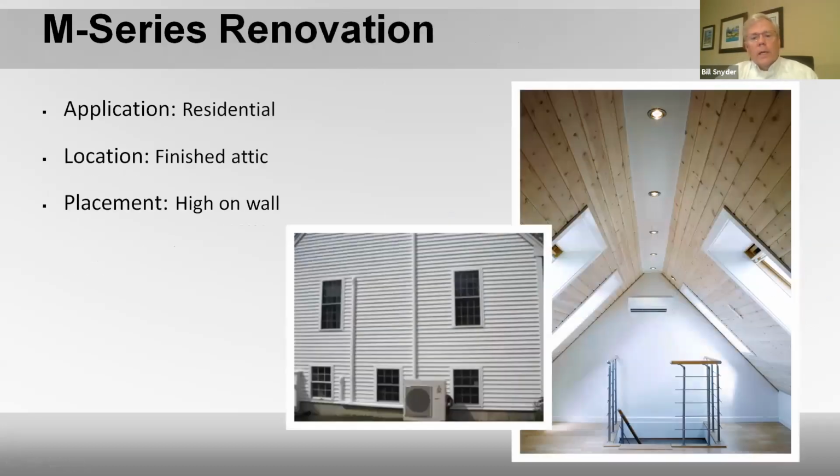And here's an example of an MXZ multi-zone unit. We know that because here's the outdoor unit, and here's line hide going up to this unit here on the 3rd floor. There's a unit on the second floor, the main floor, and then there's a unit down here in the basement. So we've got at least 3 zones coming off of this unit. And this one obviously had to be mounted on a flat vertical wall. If you mounted it up here, the water would pour out of it from the drain pan.